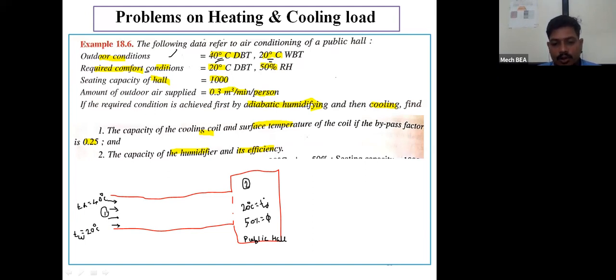The sitting capacity of this hall is 1000 persons, and the amount of outdoor air supplied is 0.3 meter cube per minute per person. Based on this, I can calculate the volume of air supplied to the air handling unit: 0.3 meter cube per minute per person, and as the sitting capacity is 1000, 1000 into 0.3 is equal to 300 meter cube per minute. This is the volume of air supplied to that air handling unit.